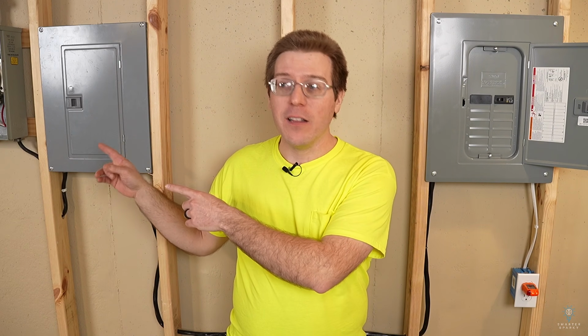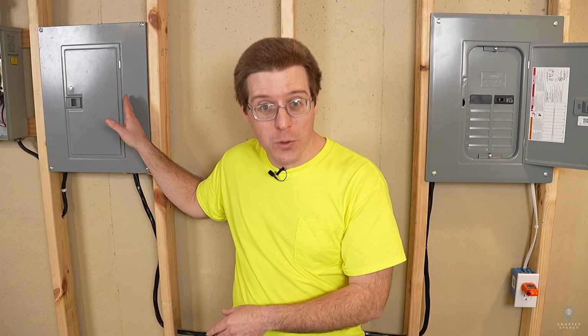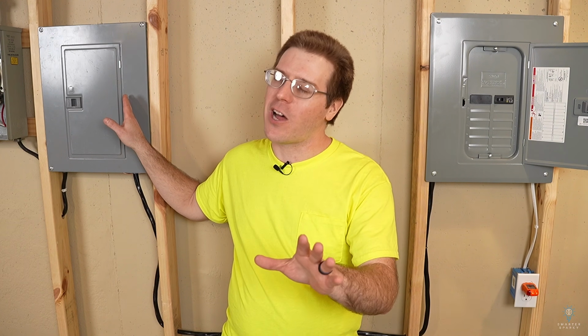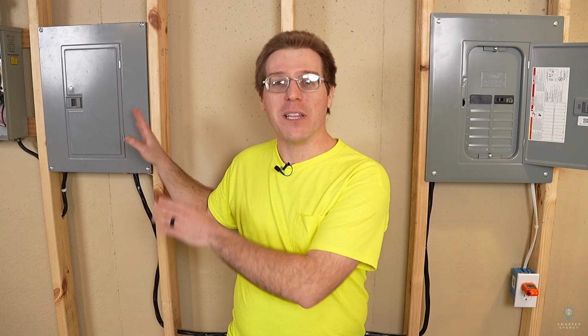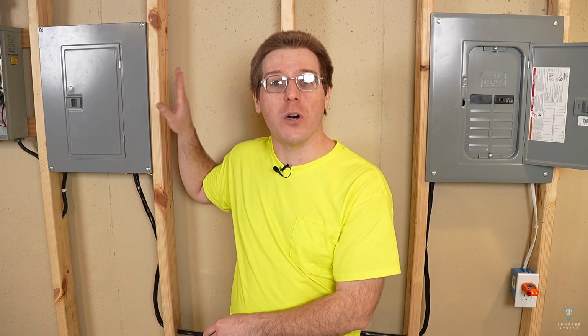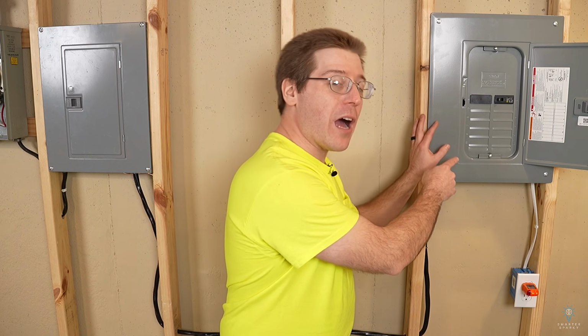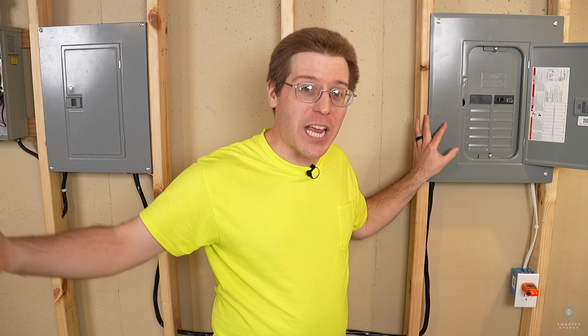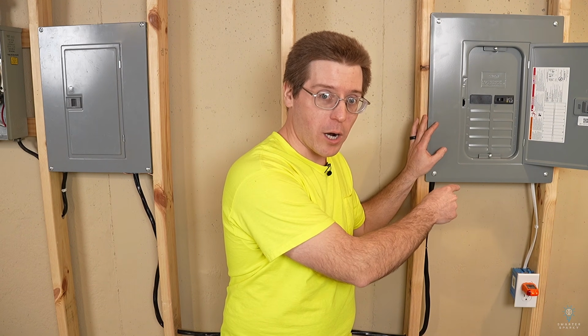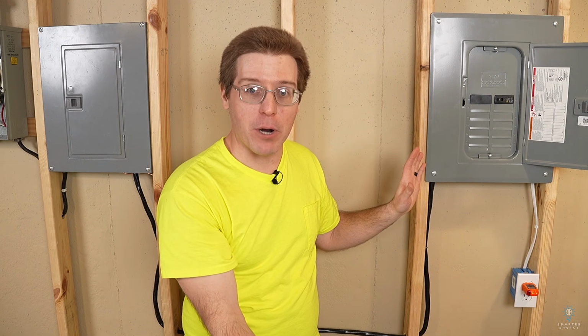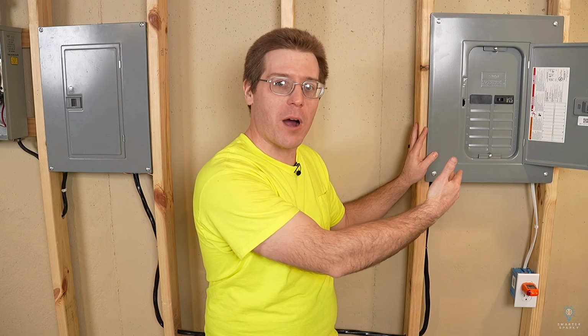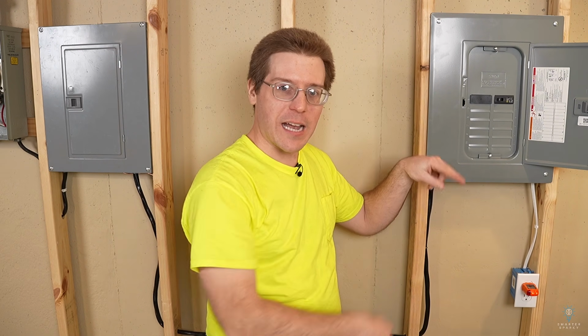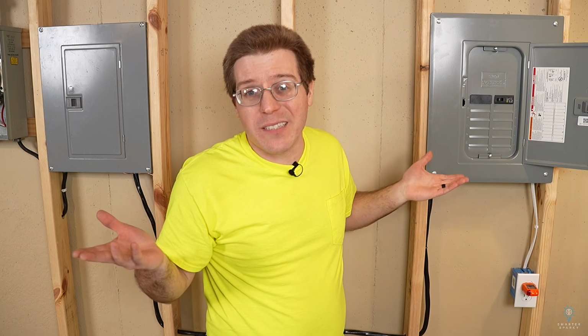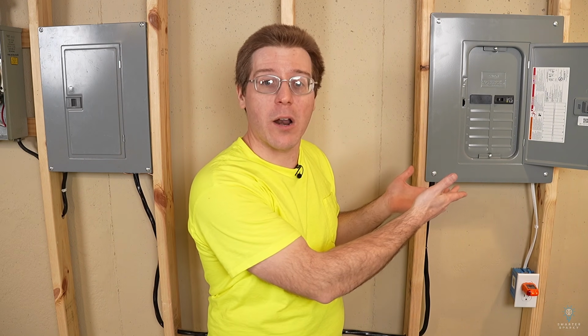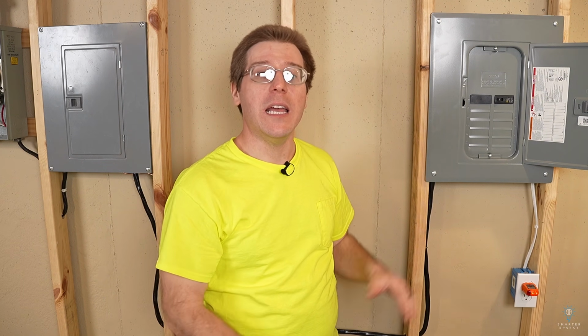In the main panel, the ground rod goes to the neutral bar. I know that's confusing. We'll talk about that in a grounding video. But the ground rod in a main panel goes to the neutral bar. The ground rod for a sub panel in a shed goes to the ground bar, and then everything else stays separate. So you have a separate neutral bar, you have your two hots landing on line 1 and line 2, and the only real difference is you'd have a ground rod also landing on the ground bar in your sub panel.